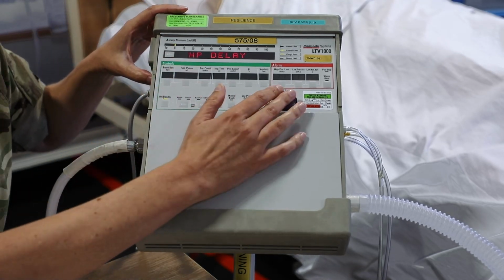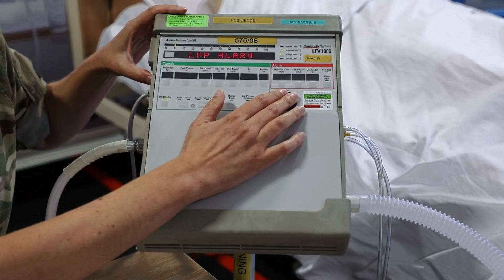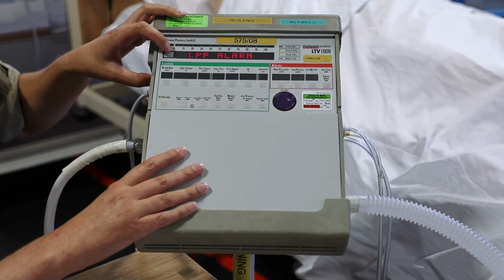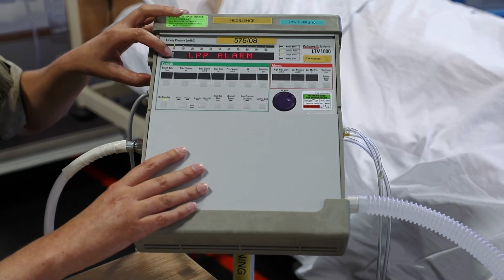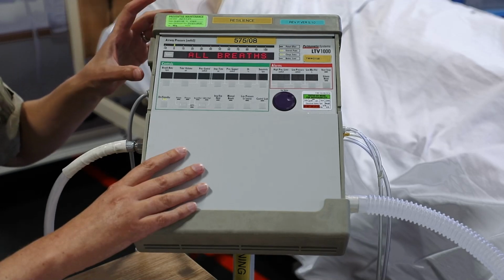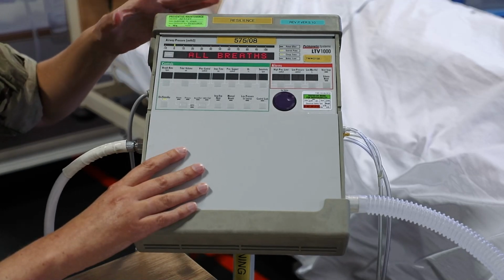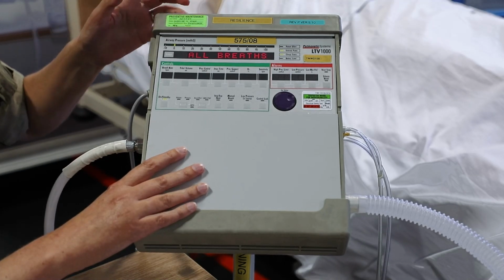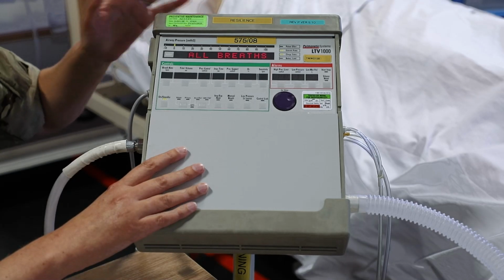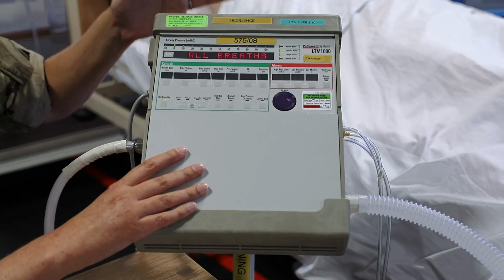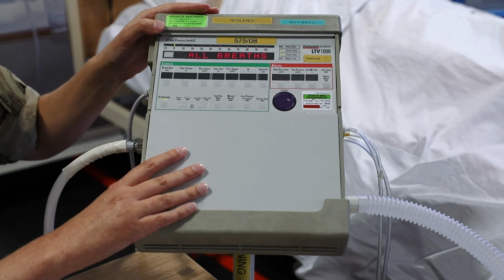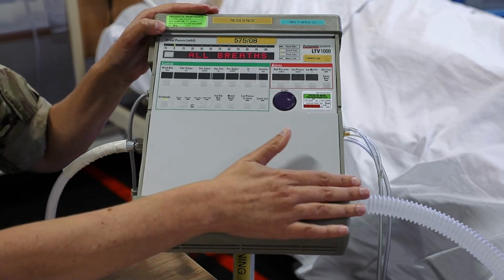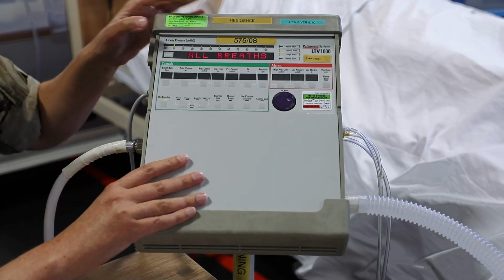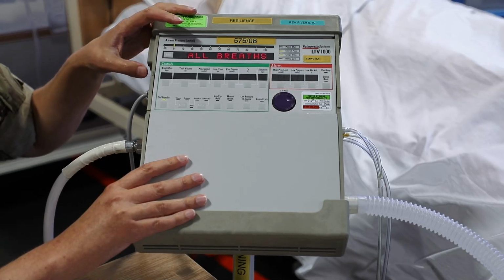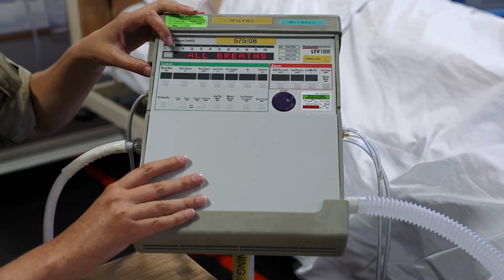Pressing select takes you back up to the top menu, turn the dial to the right, and we're into our low peak pressure alarms. Now this, if we select it, should be set on all breaths. The way I remember that low pressure alarm is it's a really useful alarm for a disconnect, because if you have a low pressure, then it's likely that you've just disconnected the circuit, or it's become disconnected at the ventilator or at the patient end. So it's helpful to have that on at all breaths so that it's always monitoring low pressure.